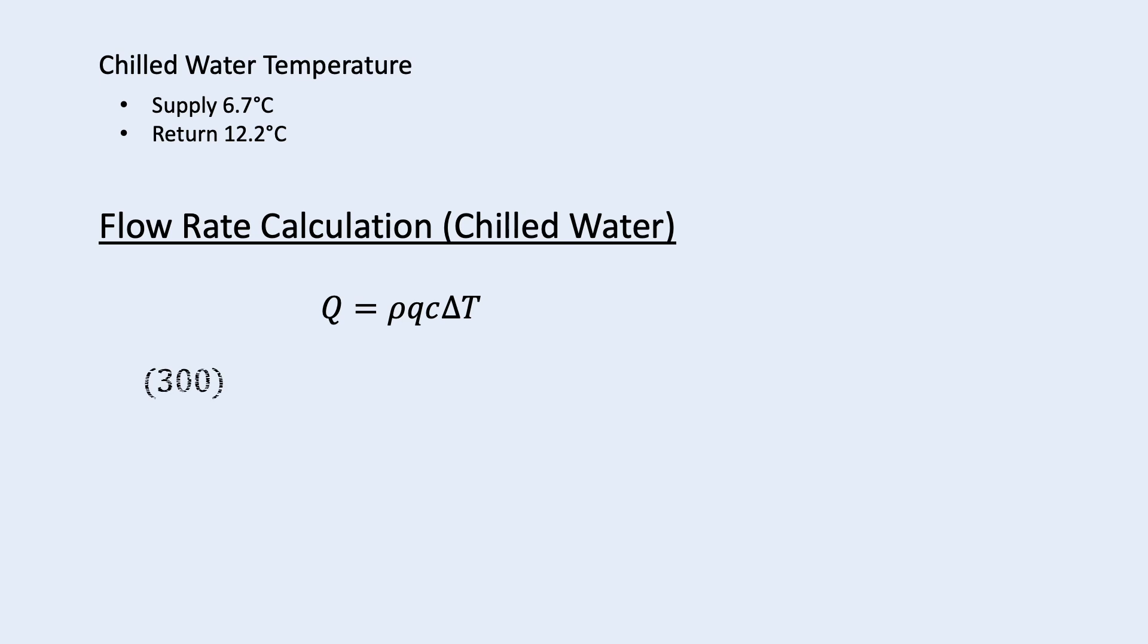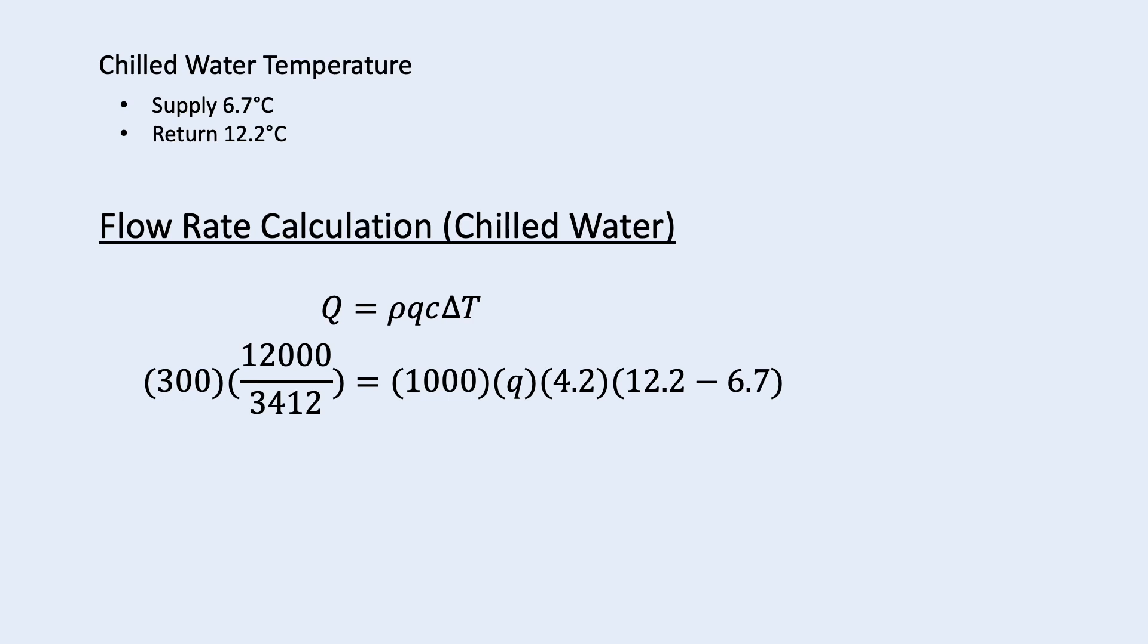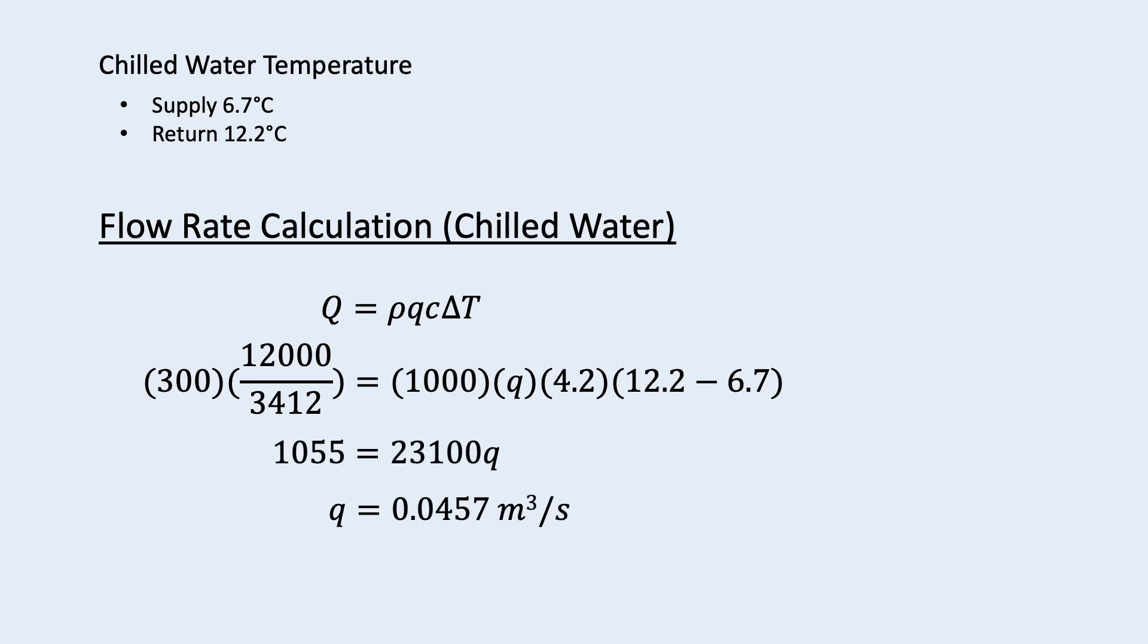Assume the chiller capacity is 300 ton. We need to convert it into kilowatt. So 300 times 12,000 will convert into BTU per hour and divide by 3412 to become kilowatt. On the other side, water density is 1000 times q, the flow rate, times the specific heat which is 4.2 times 12.2 minus 6.7, the chilled water supply return temperature difference.